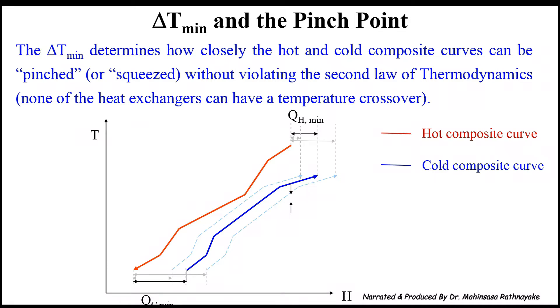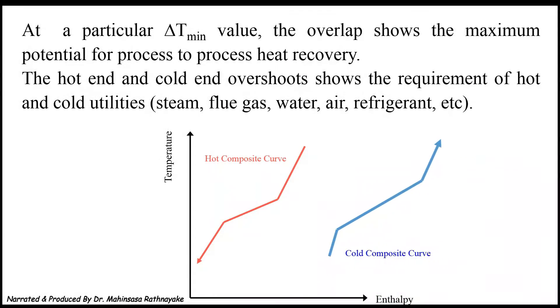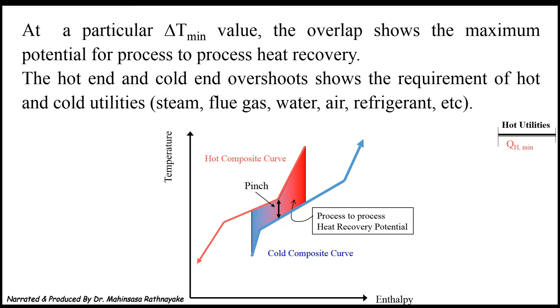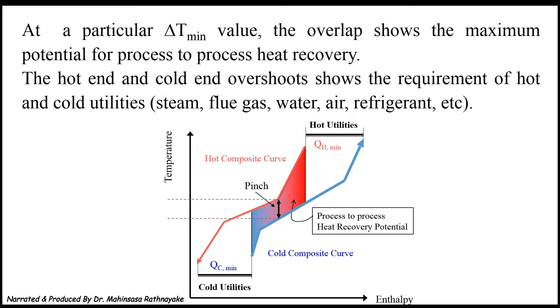Delta T minimum determines how closely the hot and cold composite curves can be pinched or squeezed without violating the second law of thermodynamics, which confirms none of the heat exchangers can have a temperature crossover. At a particular delta T minimum value, the overlap shows the maximum potential for process-to-process heat recovery, while the hot end and cold end overshoots show the requirement of hot and cold utilities. Therefore, from the TH diagram for a system, we can find the minimum hot utility requirement, the minimum cold utility requirement, and the process-to-process heat recovery potential. The rule of thumb in placing the composite curves in the TH diagram is following up the pinch point.